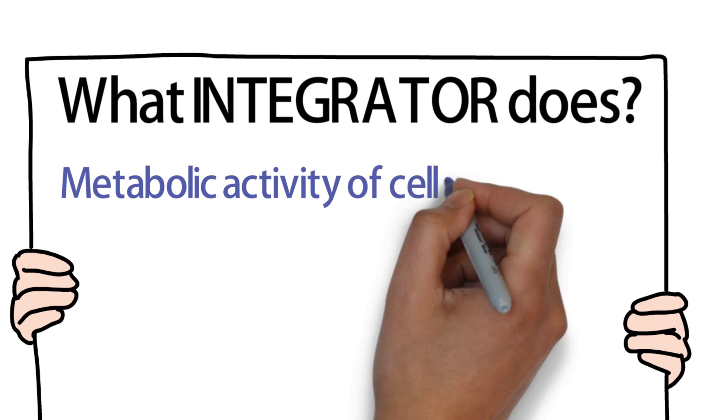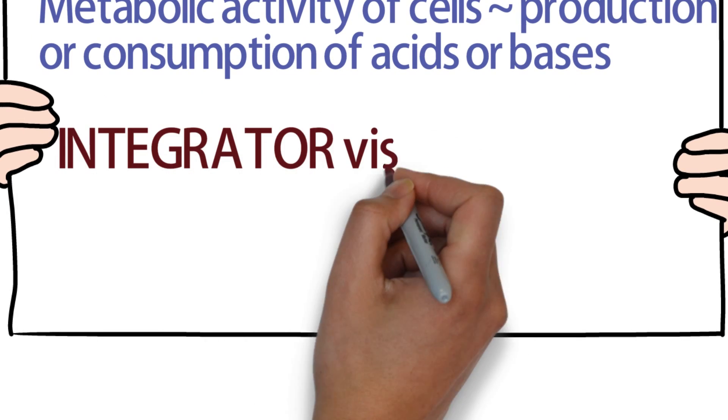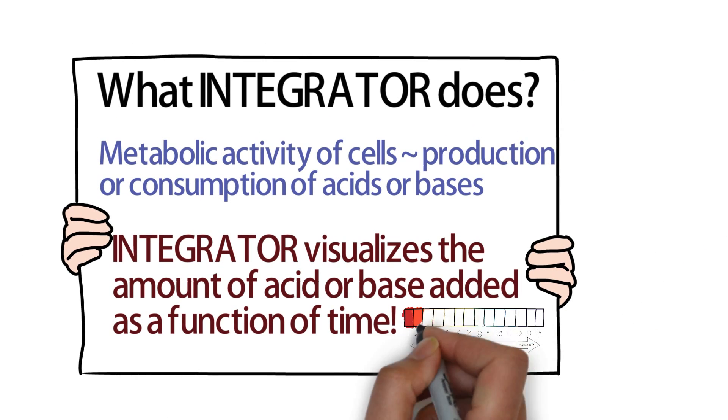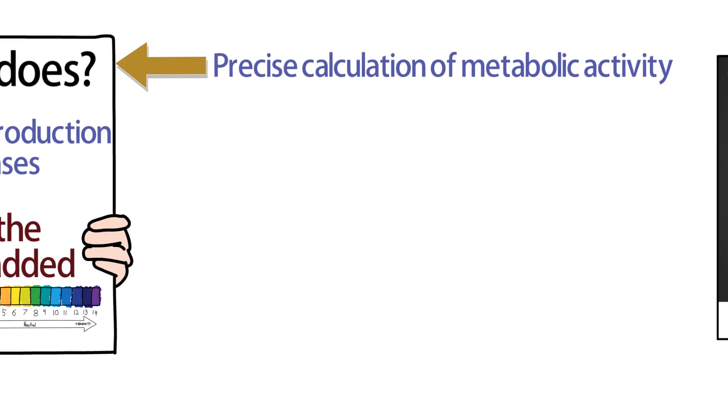How does the integrator overcome the disadvantages of OD measurement? Metabolic activity of cells is related to production or consumption of acid or base. The integrator visualizes the amount of acid or base added as a function of time. Metabolic activity can be measured with much better precision. The integrator provides important information about culture growth, its kinetics, and time of completion.